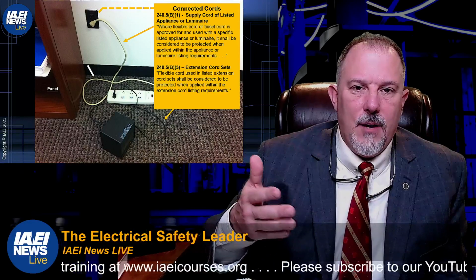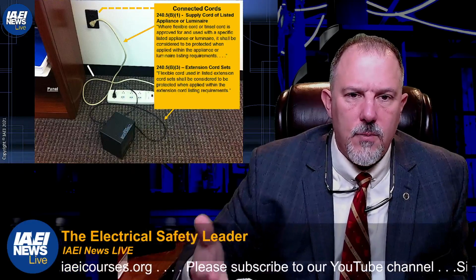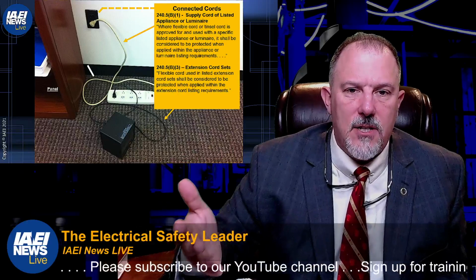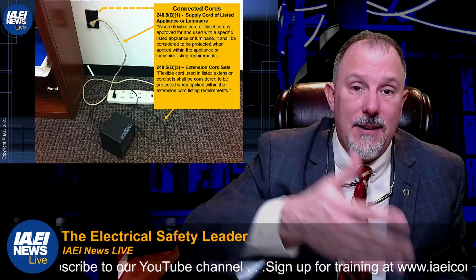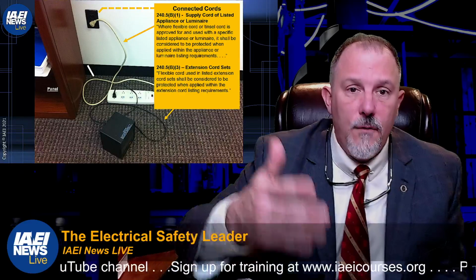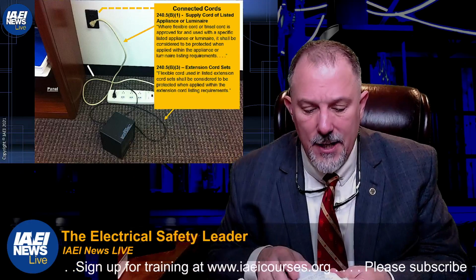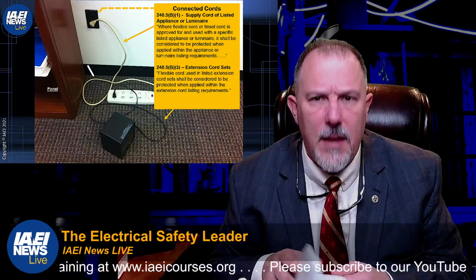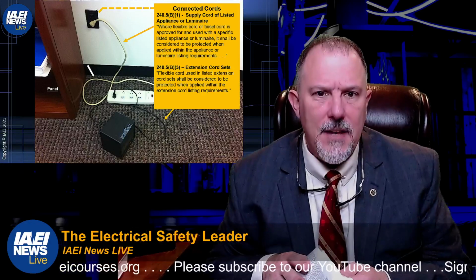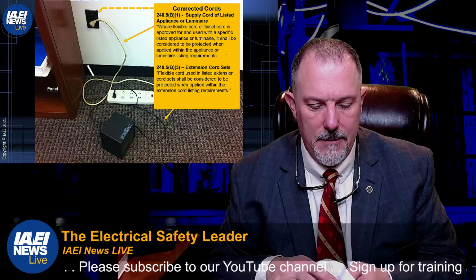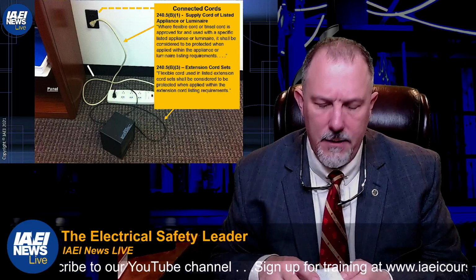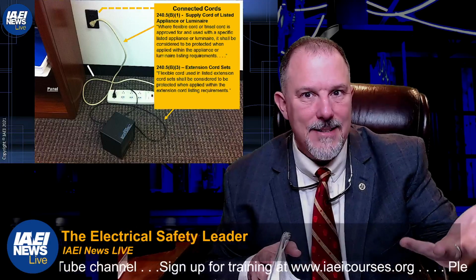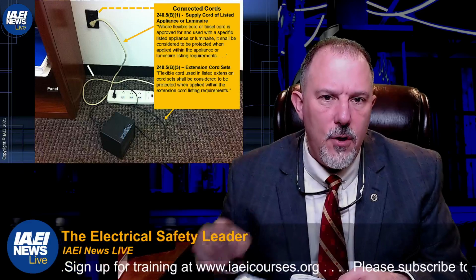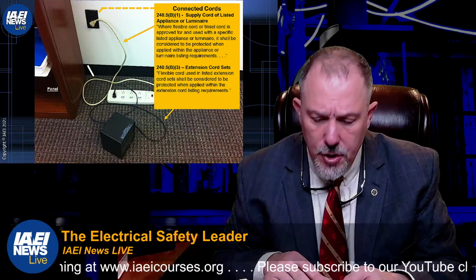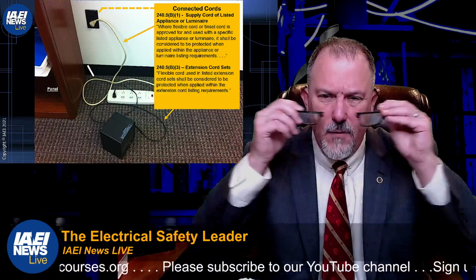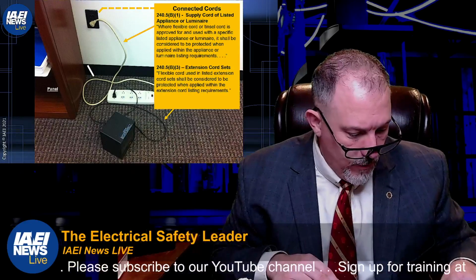240.5(B)(1) says that where you have flexible cords or tinsel cord approved for use with specific listed appliances or luminaires, it shall be considered to be protected when applied within the appliance or luminaire listing requirements. Because 240 is overcurrent protection, I would ask, how do I get the protection of the actual luminaire, the attached appliance? It's not in 210, and I can't say it's 210.8, because that's people protection. So I go to 240.5(B)(1), because 240 is overcurrent protection, and you would think overcurrent protection of the luminaire would be there.